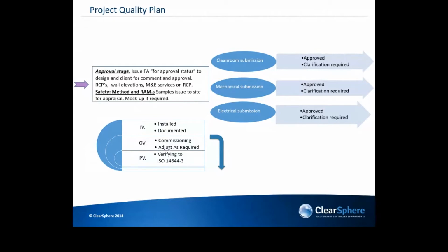Working with Connor and the guys on site here for the hospital, what we looked at was: yes, you have your design criteria to start off with, but as you work through and do your smoke visualizations and recovery tests, you might find dead spots in some areas of the room, so you can adjust. It's not just a matter of setting up the system to operate per the P&IDs — it's a dynamic situation where you adjust as required to get the best performance out of the room. Then you move on to carrying out all your performance verification testing to the ISO standards, part 3.